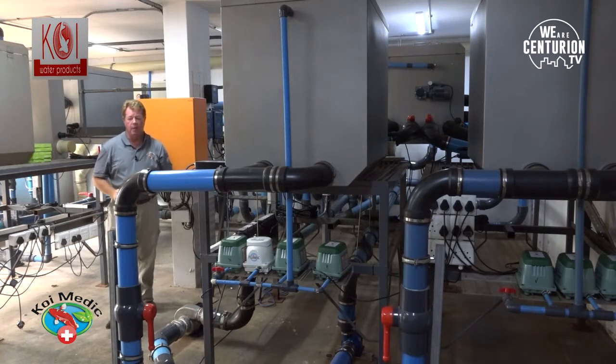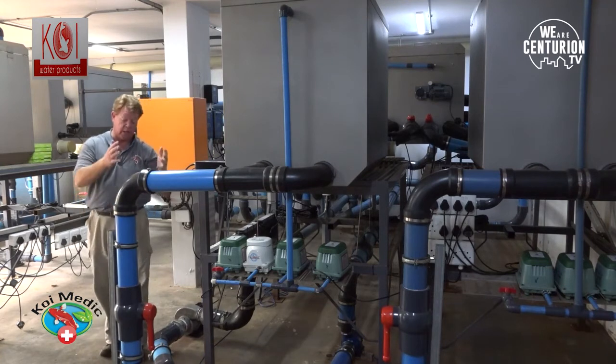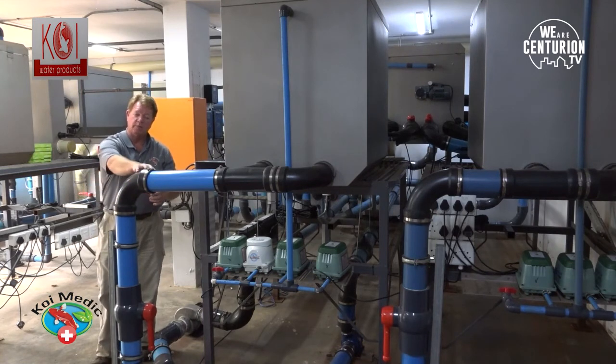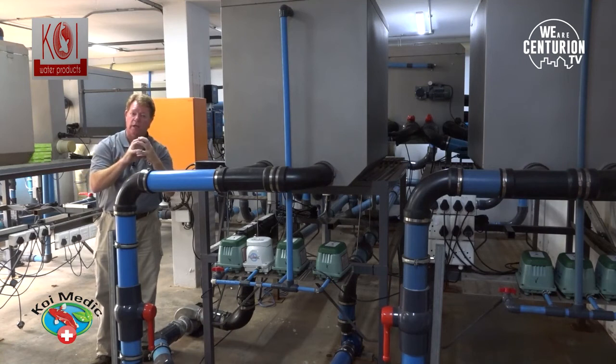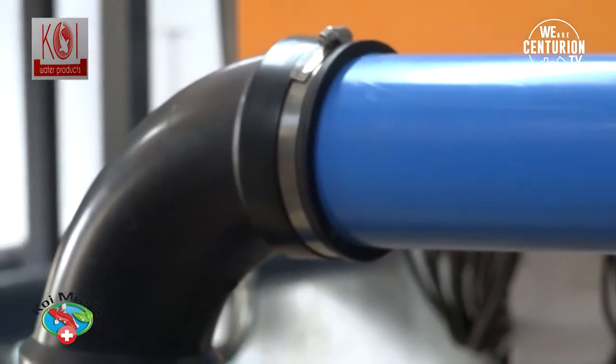As you can see, the piping and everything has been done extremely professionally. And you'll notice also that there are no 90-degree bends here. It's all slow bends. The very important thing is, even this piping on the inside has been tapered to such a point before it gets clamped on here that when they glue it together, the flow of the water is not being interrupted. So even the slightest bit on the inside that is causing a cavitation is a no-no. So the piping has to be done by an expert. But all slow bends, because it's a gravity-fed system.